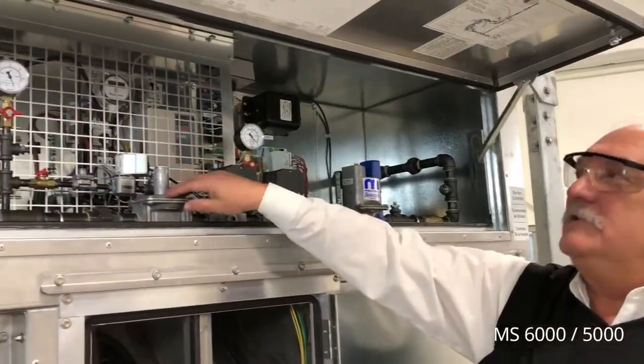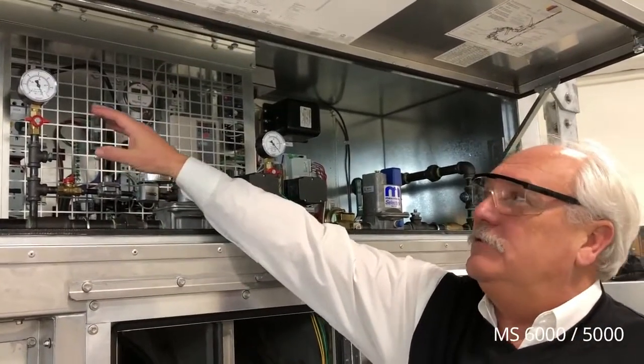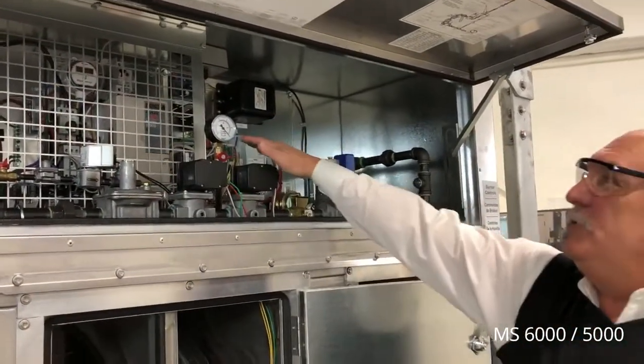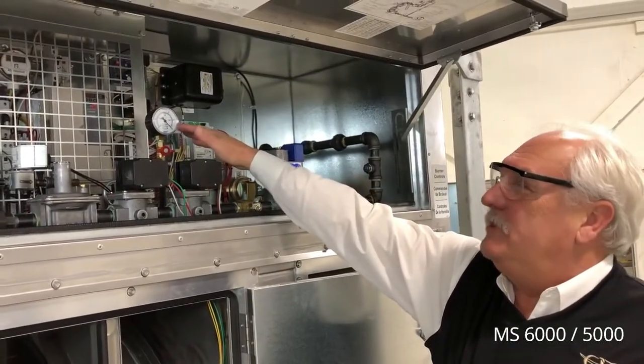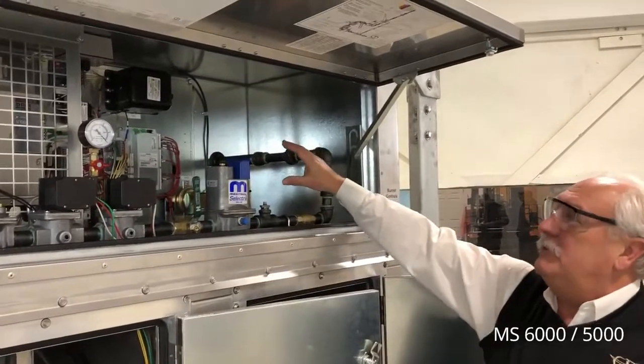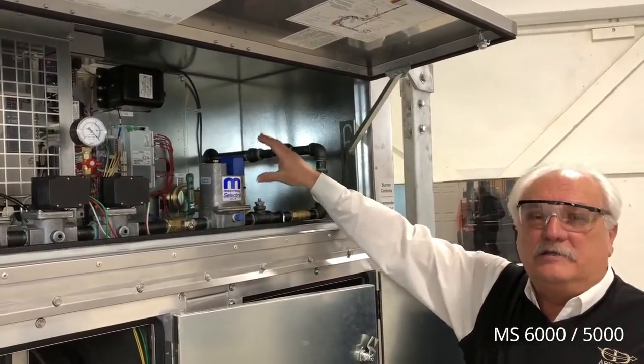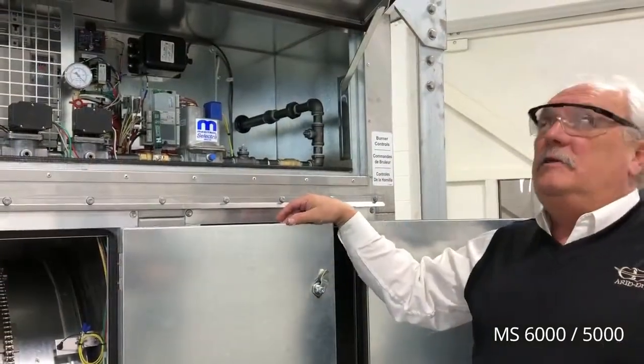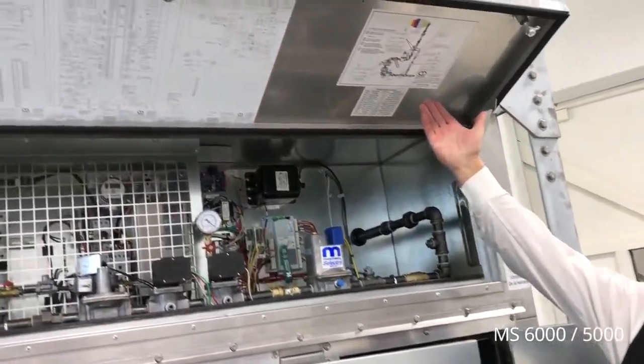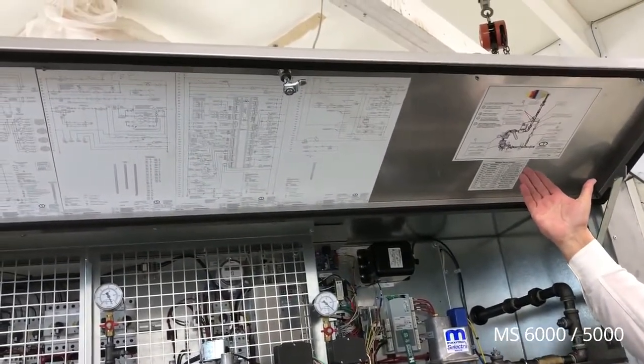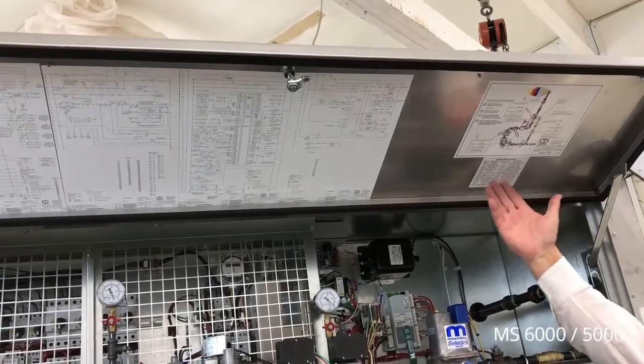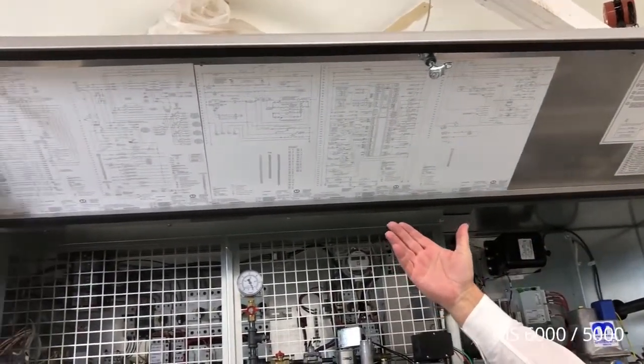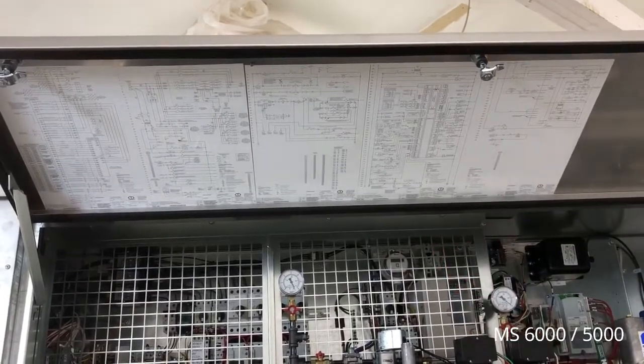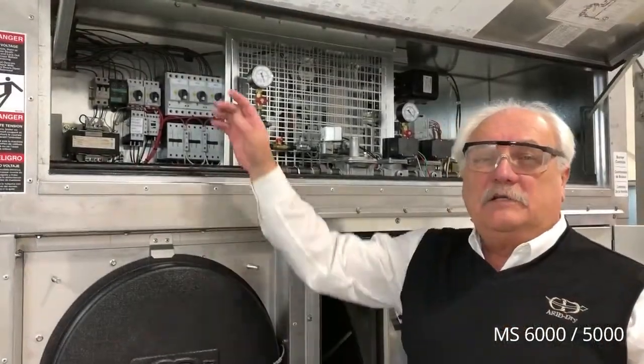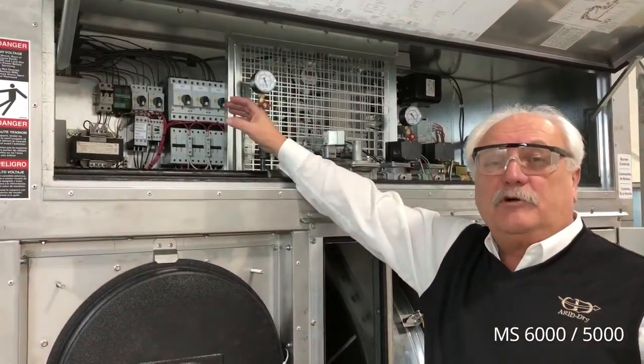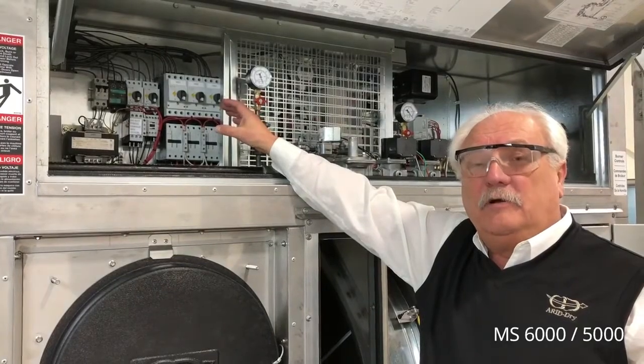The gas train is also housed in this compartment. We have an inlet pressure gauge that allows you to witness your inlet gas pressure. A burner manifold gauge, which shows us the burner manifold gas. And the gas train components and flame safeguard system are all located in this compartment. On the back of the access door, we have a gas manifold drawing with the normal pressures for reactivation operation. We also have a complete wiring schematic of the components in the dehumidifier. When accessing high voltage components, be sure to wear personal protective equipment as required by local code and your company.